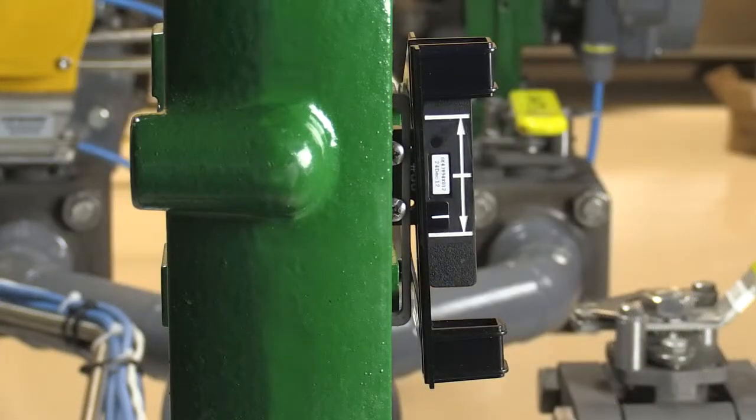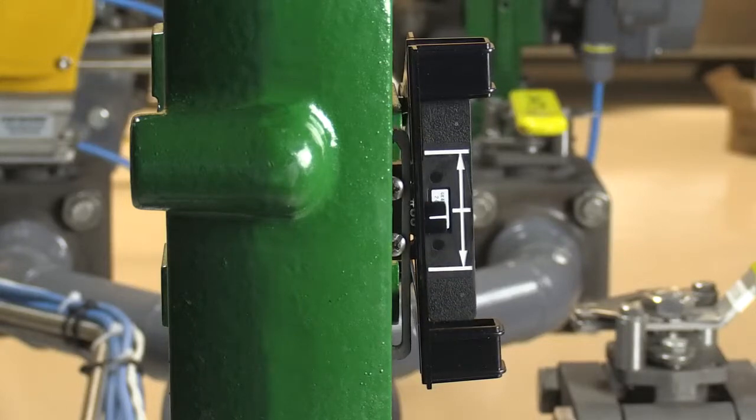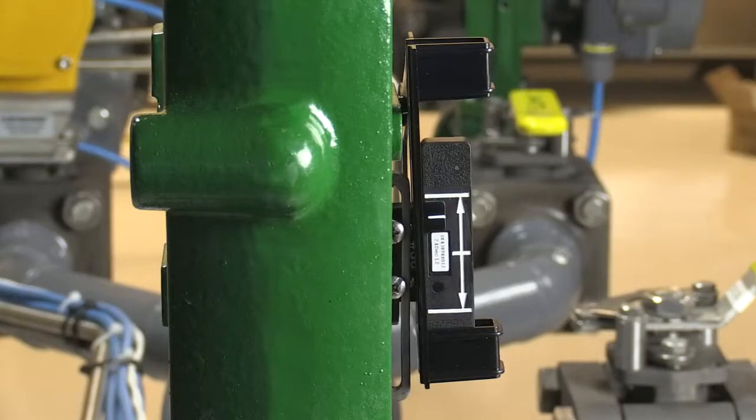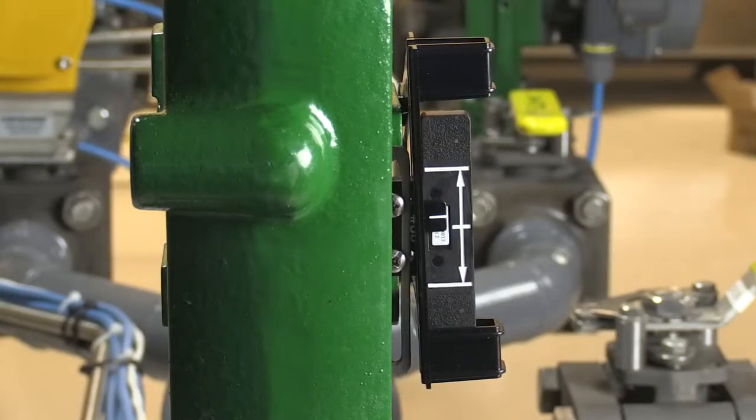Once we've aligned the magnetic array, we'll stroke the valve one complete cycle to make sure the template's white line stays within the lines on the array for the full travel distance.